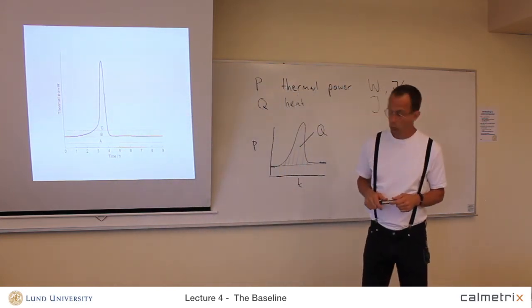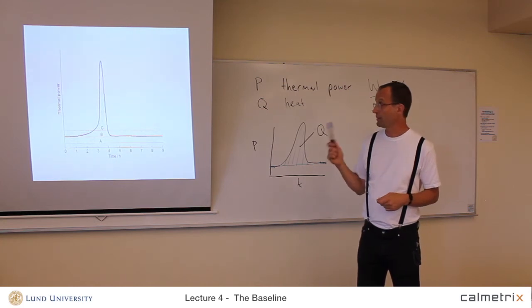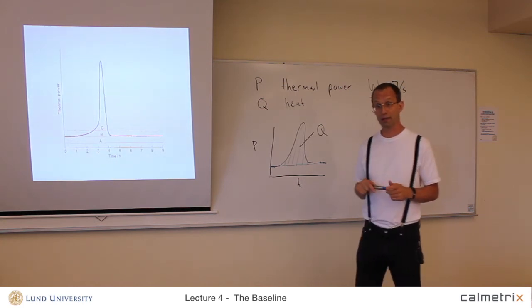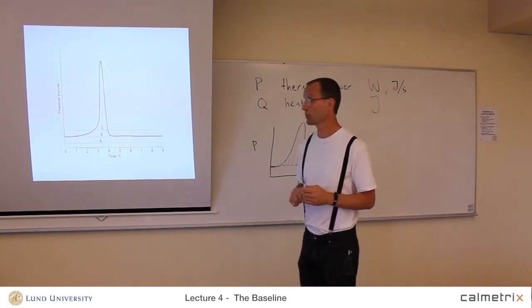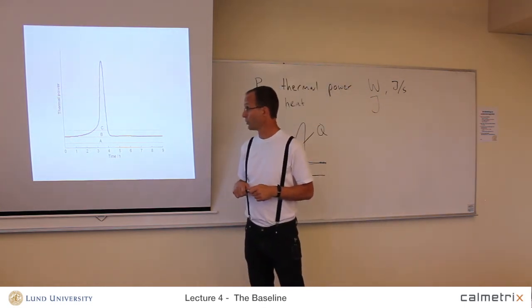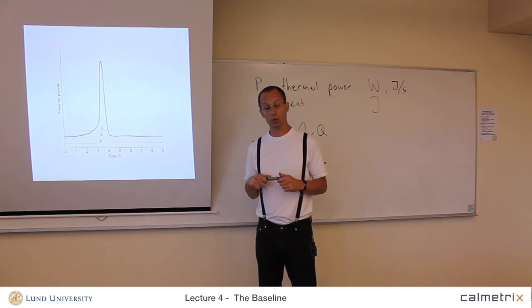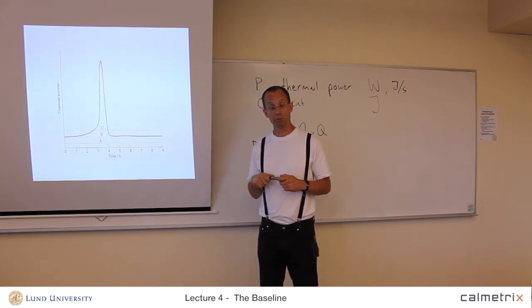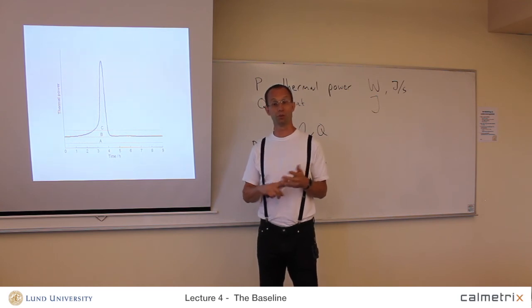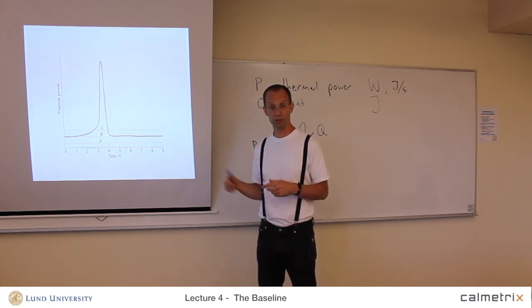So that was the baselines. We should measure long-term baselines — at least 24 hours. That is very important. In the next lecture, I will cover another important parameter: the calibration coefficient. You need both the baseline and the calibration coefficient to evaluate most measurements.